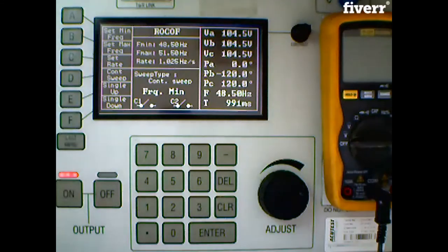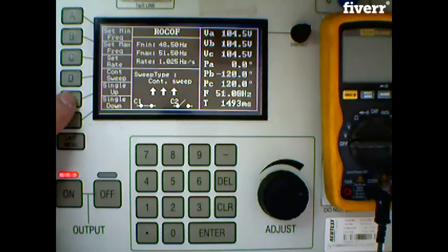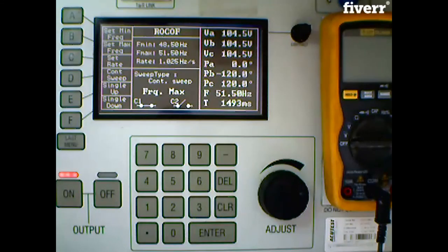Now, don't forget, we can't swap the filter settings again, because you've only got one setting. Once you've got it where you need it, you've got to leave it, because you can't keep changing it for different tests. You've got to leave it where it is. So we're now going to come up. 1493. So our up is 1493. And again, at the bottom of my test sheet, because this is another fail in exactly the same situation, on the increasing frequency, I would write down that my increasing frequency was giving me slow times with the settings that were requested by the test sheet.